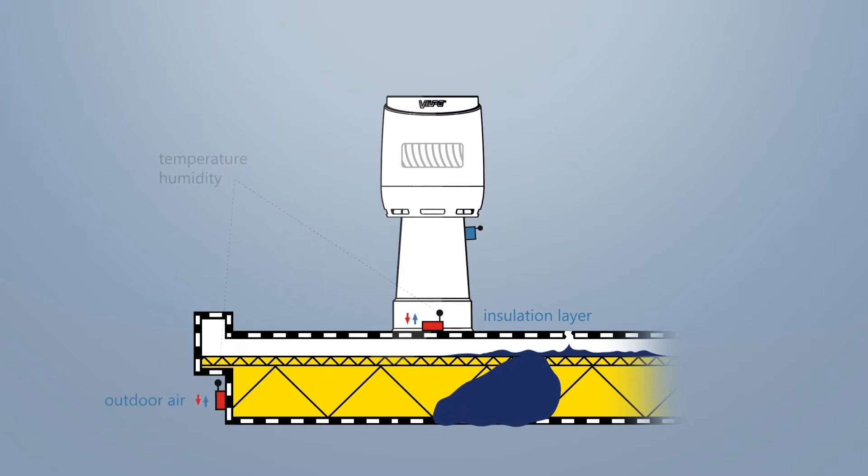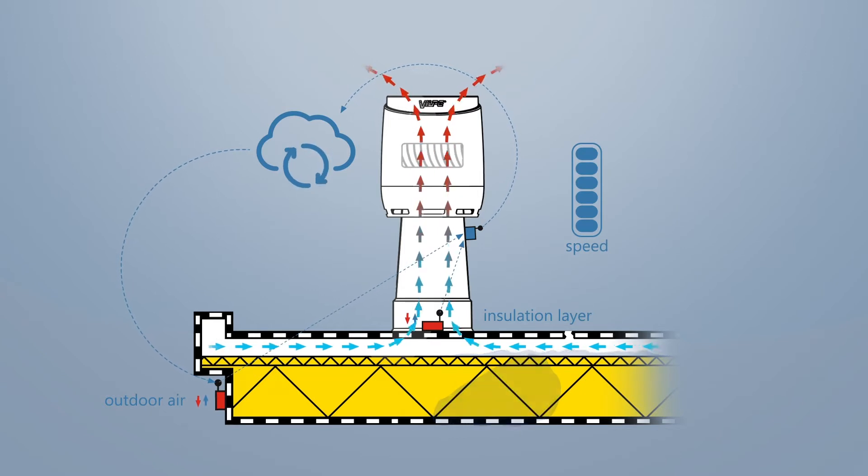This information is sent to the control unit and ends up on the Vilpe cloud service where it is analyzed. If the system detects excess humidity in the insulation layer, the roof fan is automatically activated to work at a higher speed until the structure is dry.